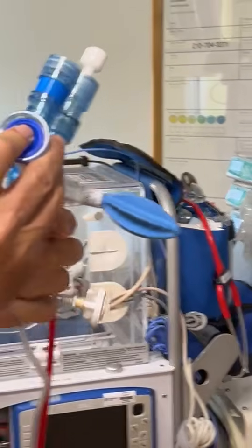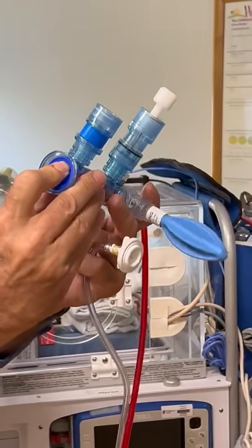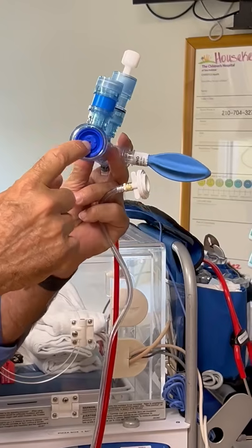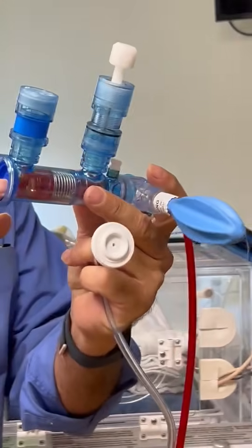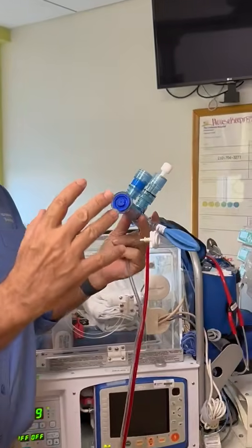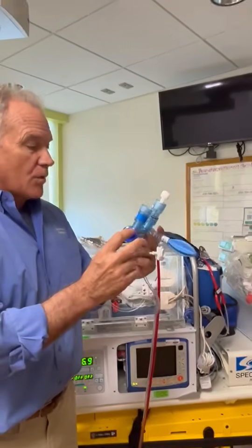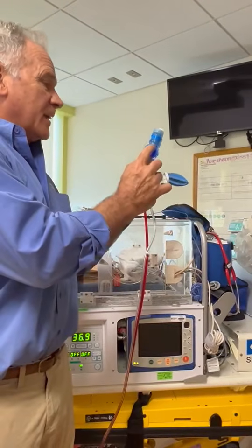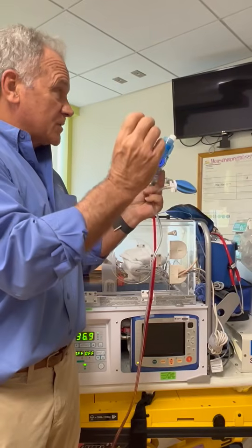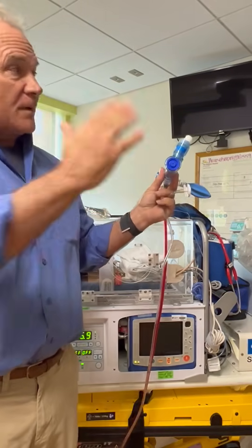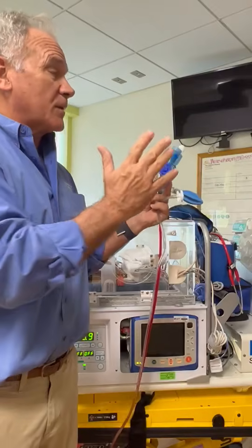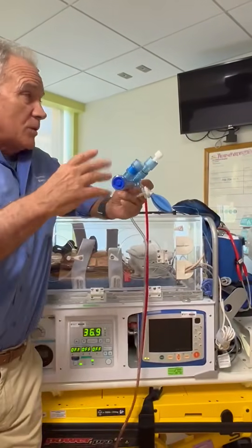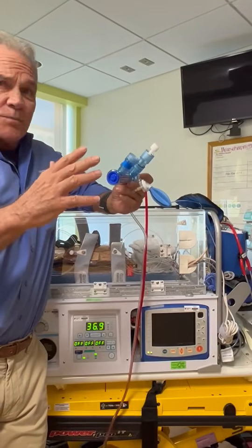And then I said it had passive exhalation, right? But it actually has active exhalation, but it's not much. So basically the way the flow interrupter works, it delivers a breath, it stops, and then the spring lets go. So, inspiratory time and then exhalation. So that's why we typically slow down the rate. And we'll talk in more detail later on about what y'all do, but I think y'all go based on disease processes here.